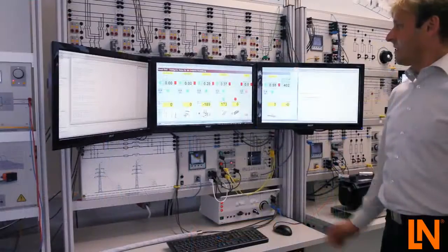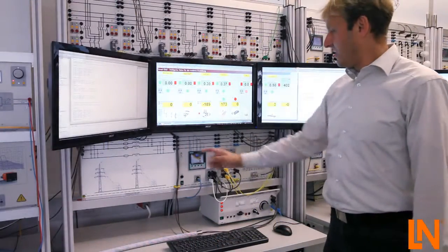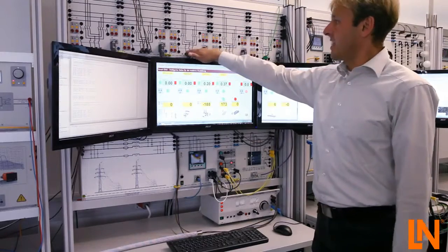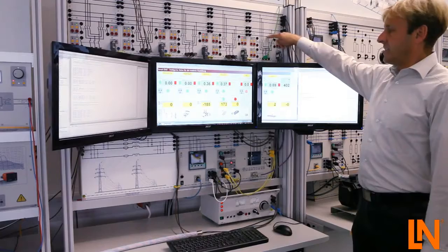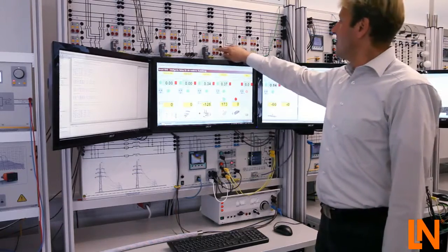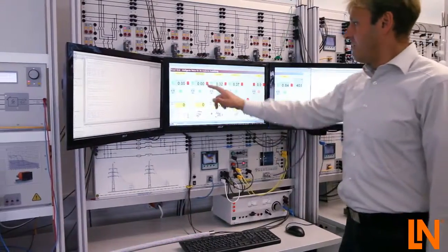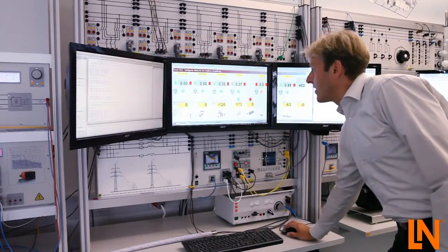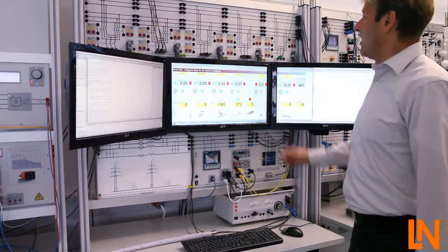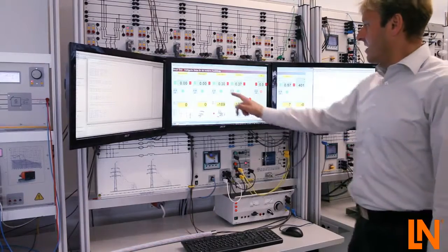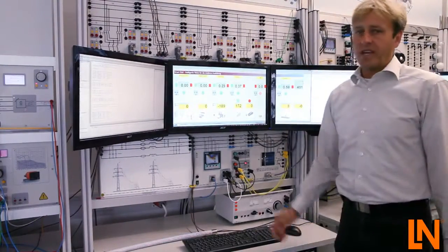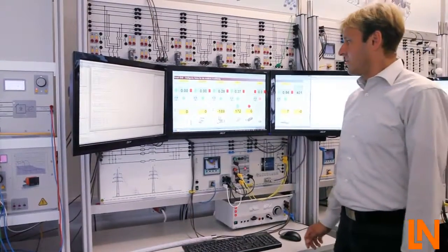Here you see the part of distribution and also transmission. Here you have the double bus bars with the outgoing and incoming feeder, as well as one double bus bar with the coupling element. You can control these bus bars by using the switches here, as well by the software. For example, I can switch off here the whole power or switch on the whole power. You can change between the two bus bars by using these power switches and the feeder. Everything can be controlled by this way. If you make an error, you hear some noise, so that you know what you like to switch is wrong.